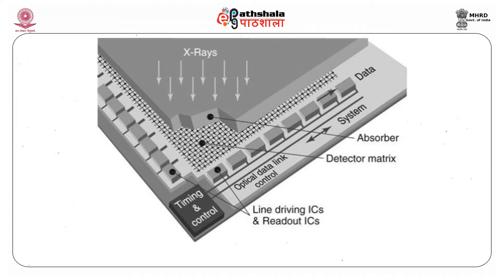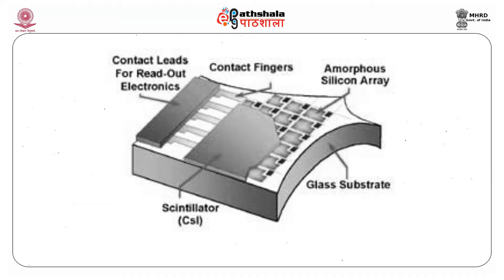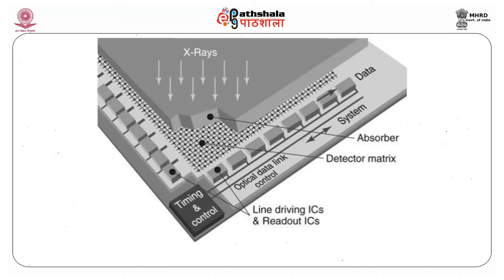As seen in this figure, the scintillation material — cesium iodide on a glass substrate — is shown as a sandwich structure. When x-rays fall onto the scintillator, it converts x-rays to light. The amorphous silicon photodiode array converts light to electrons, forming a bucket of electrons for each pixel. The TFT acts as an electronic switch, collecting the charge from the photodiode at every pixel and reading it out into the electronic system so it can be displayed on a monitor.